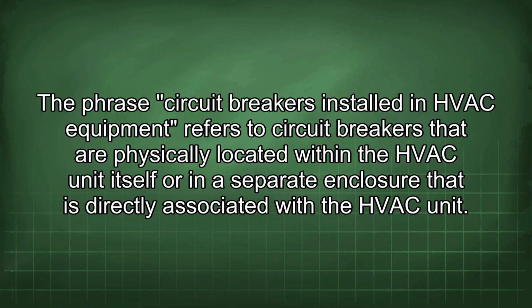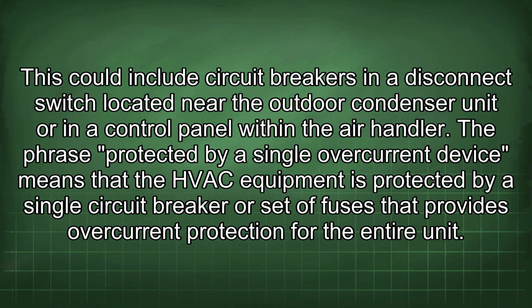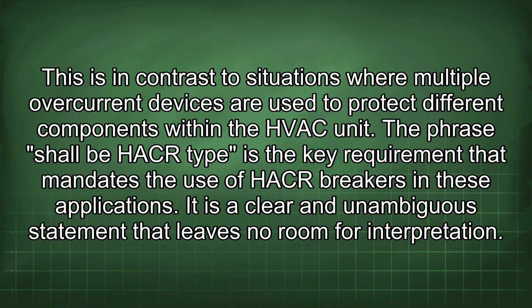The phrase circuit breakers installed in HVAC equipment refers to circuit breakers that are physically located within the HVAC unit itself or in a separate enclosure that is directly associated with the HVAC unit. This could include circuit breakers in a disconnect switch located near the outdoor condenser unit or in a control panel within the air handler. The phrase protected by a single overcurrent device means that the HVAC equipment is protected by a single circuit breaker or set of fuses that provides overcurrent protection for the entire unit. This is in contrast to situations where multiple overcurrent devices are used to protect different components within the HVAC unit.